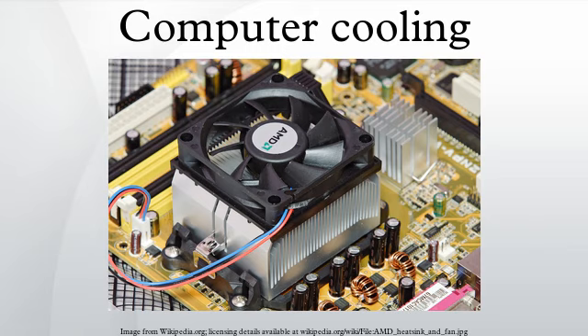Other techniques. Liquid submersion cooling: an uncommon practice is to submerge the computer's components in a thermally, but not electrically, conductive liquid. Although rarely used for the cooling of personal computers, liquid submersion is a routine method of cooling large power distribution components such as transformers. It is also becoming popular with data centers. Personal computers cooled in this manner may not require either fans or pumps, and may be cooled exclusively by passive heat exchange between the computer hardware and the plastic box it is placed in.